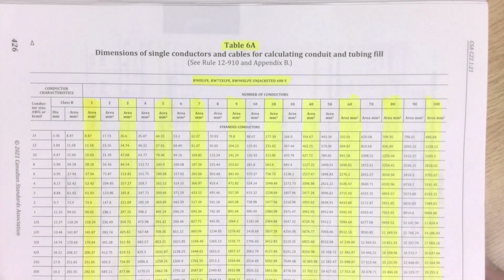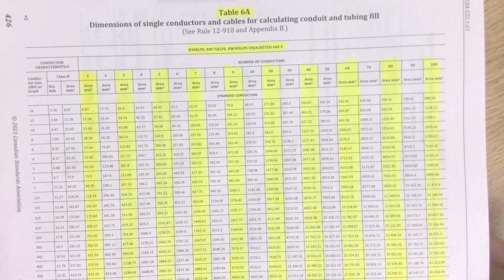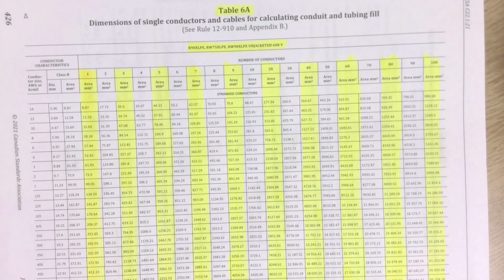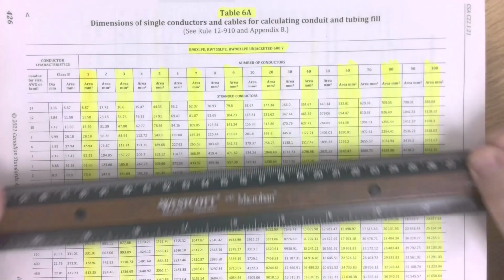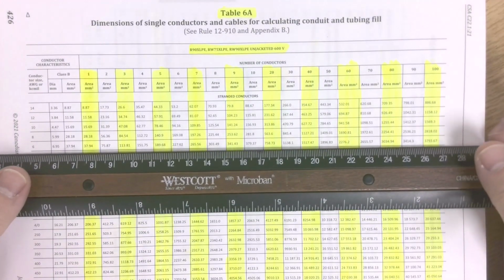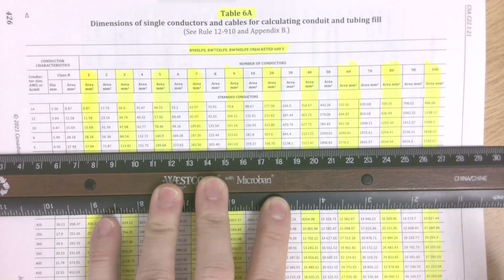Now, there's a couple approaches to do. We could just do this mathematically, sort of some ratio math, if you want to think back to that first theory module. But just sort of to make sure I'm going to be in the right range, I know that the most area I could fill is 1,255.62 millimeters squared. That's what's 40% of that conduit.